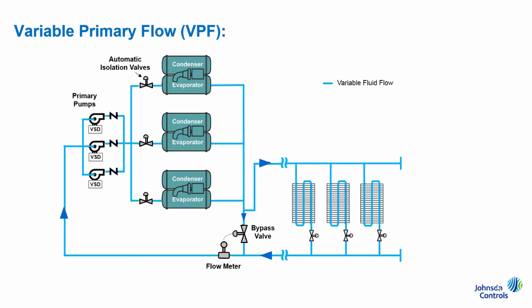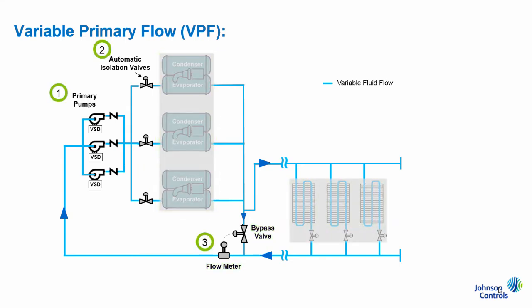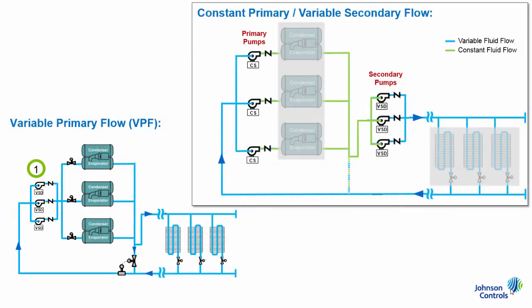Here's a typical design. Let's discuss the main components: the pumps, isolation valves, and the bypass valve flow meter tandem. Furthermore, you'll notice the chiller and air handling equipment. These components support the building load, but remain constant independent of the pumping design, so we won't be focusing on them. Okay, first the pumps. The two key differentiators here, versus a primary-secondary system, are that all VPF system pumps are variable speed, and they're all located upstream of the chillers.